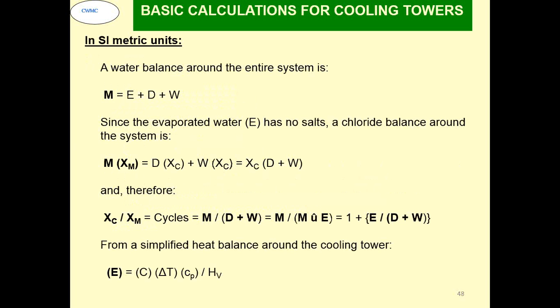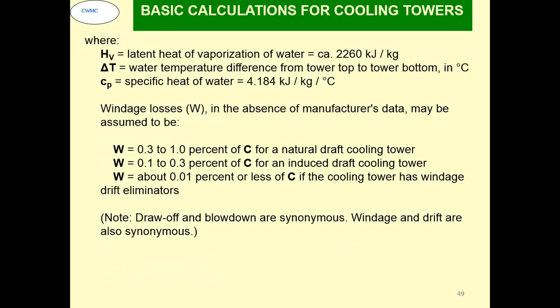Calculations are based on a water balance diagram, and on the system makeup is E plus D plus W. This is the derivation out of that, which says that XC by XM, the cycles, is equal to M by (D plus W), which equals 1 plus E by (D plus W). From a simplified heat balance diagram, E becomes C times delta T times Cp divided by Hp. Hp is the latent heat of vaporization, which is about 2260 kilojoules per kg. Delta T is the water temperature difference from tower top to bottom in degrees centigrade. Cp is the specific heat of water, about 4.184 kilojoules per kg per degree centigrade for normal water, river water or fresh water.